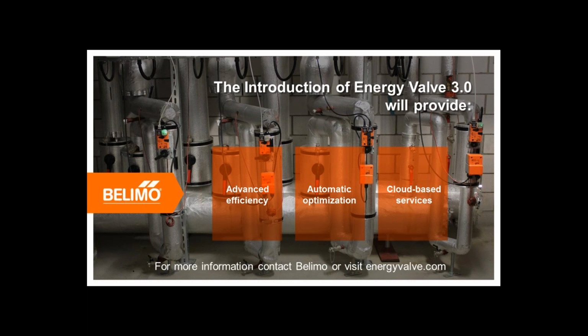Okay. That kind of answers the second question. What are the major causes of low delta T? Yep, so those are some of the ones we covered, but they can range from valves which are oversized, control valves or coils which are basically sized for a design load. We typically don't hydronically dynamically balance our systems. We balance them at a static set point, which can lead to some differential pressure issues. Also, coils can degrade, get dirty, foul up, get dusty, the filters aren't changed. All these issues can cause low delta T syndrome in buildings.